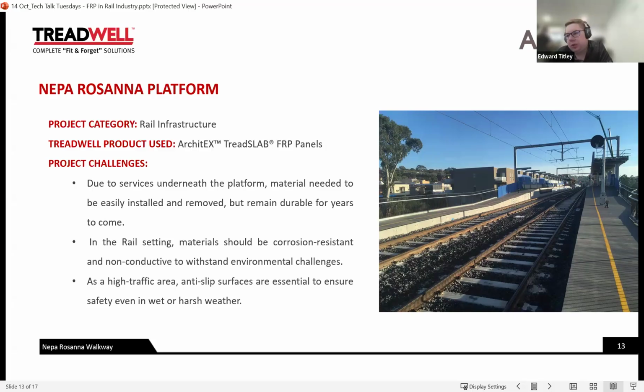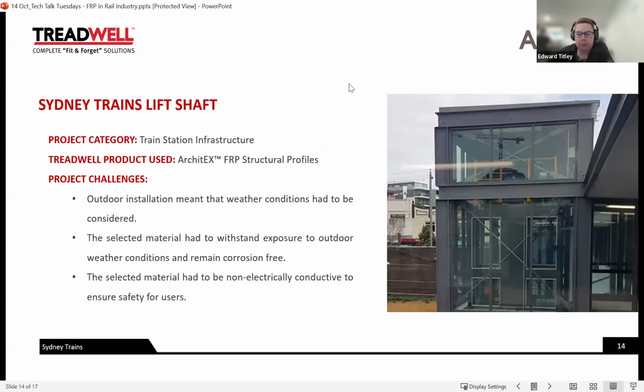It's an interlocking board with a tongue and groove arrangement, but it's designed so that if I have, say, four panels adjacent to one another, side by side, I can remove one of the middle panels without having to remove the outside one. So if there's any maintenance access needed to these services, the client is able to do a very non-invasive removal process, get the access they need, and then simply reinstall and reinstate that platform. It also has a P5 slip rating, which resolves any concerns around slipperiness of some materials if it's wet. This one here is a Sydney Trains substation, from memory.